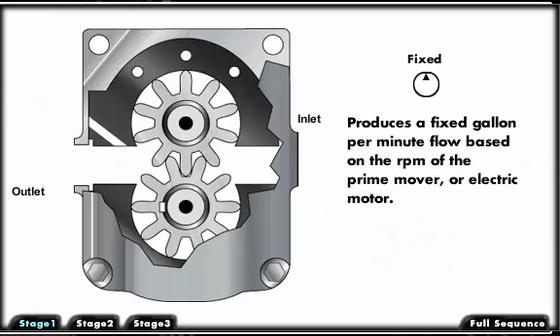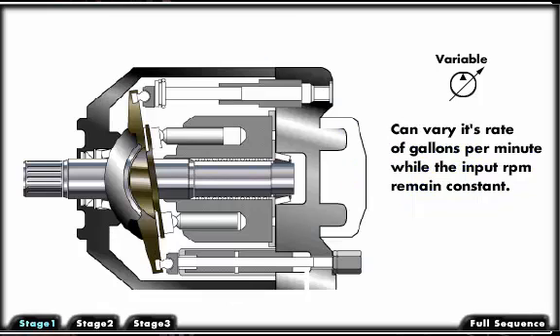There are two types of positive displacement hydraulic pumps: a fixed pump, which produces a fixed gallon per minute flow based on the RPM of the prime mover or electric motor, and a variable pump, which can vary its rate of gallons per minute while the input RPM remain constant.